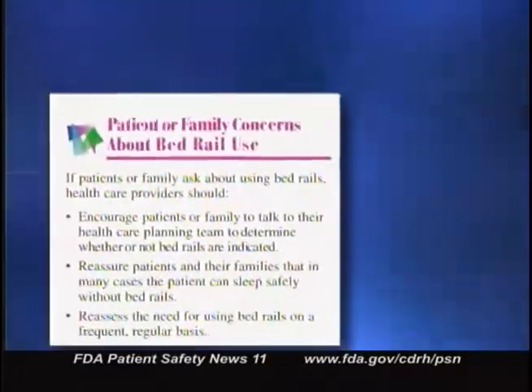This brochure gives suggestions on how to keep patients safe with or without bed rails. When bed rails are used, the brochure advises performing an ongoing assessment of the patient's physical and mental status and closely monitoring high-risk patients. Other strategies include lowering one or more sections of the bed rail, such as the foot rail, and using a proper-size mattress or a mattress with raised foam edges to prevent patients from being trapped between the mattress and the rail. When not using bed rails, suggestions include using beds that can be raised and lowered close to the floor and keeping the bed in the lowest position with wheels locked. We'll be talking about other ways to improve bed safety in future programs, including additional resources from the Hospital Bed Safety Working Group.